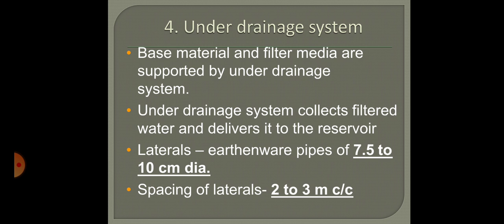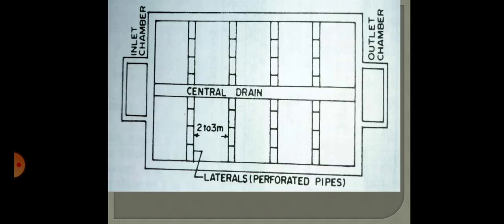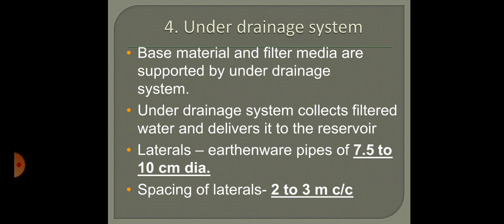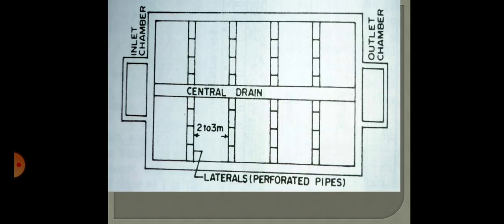The filter media and base materials are supported over an under-drainage system. This system collects the filtered water and delivers the clean water to the reservoir. The lateral drains are made of earthen pipes or perforated pipes of about 7.5 to 10 centimeters in diameter, or patented drain devices, spaced at 2 to 3 meter centers.